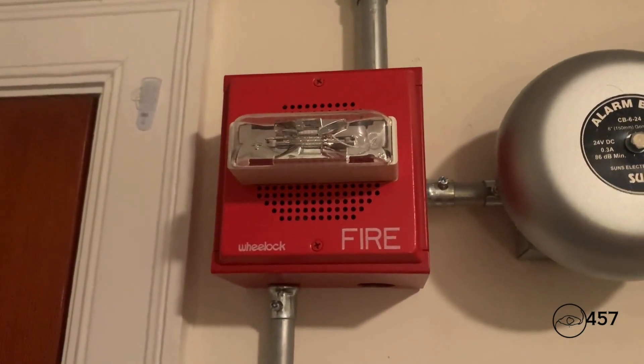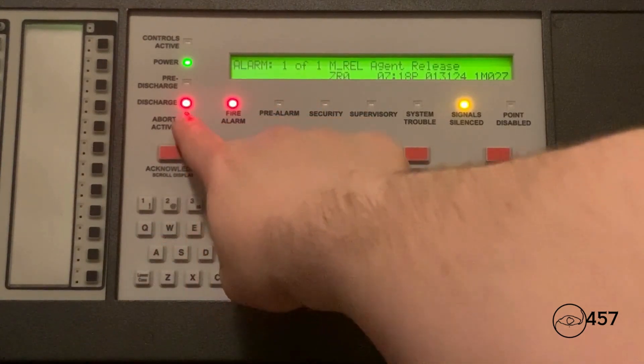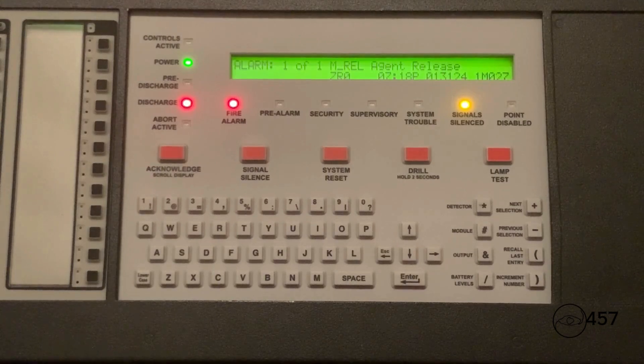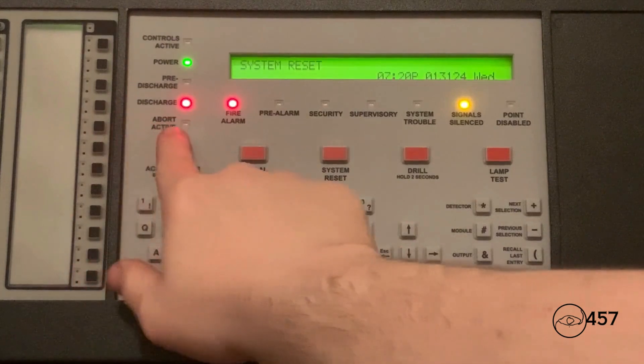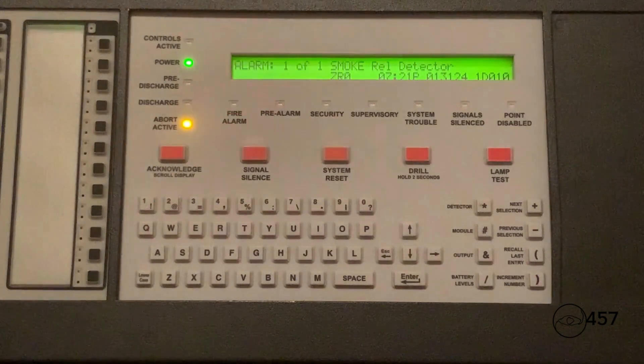All right, I will reset the system. Before I end the video, I will show y'all the abort active LED light up. I'm going to activate the smoke detector and then press and hold down the abort switch, and that abort active LED will light up. Let's reset the system. Code red, code red — the signal you have just heard indicates that the suppression releasing system has been activated.